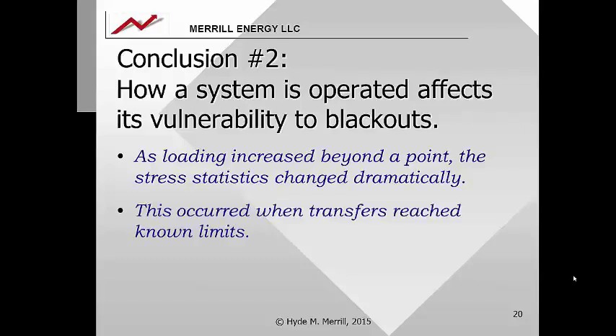This occurred when the transfers between these two pieces of the system reached known limits. I know this system fairly well, I've done studies on it. Using conventional tools, I know roughly how much power can be transferred from one side of the system to the other. The stress statistics reach their tipping point at about the point where those transfers reach the known transfer capability of the system.